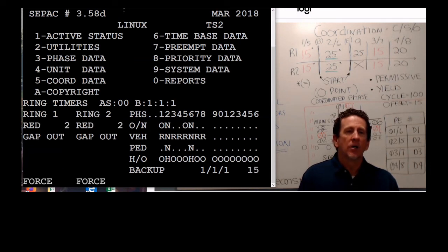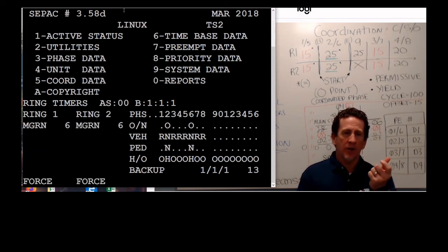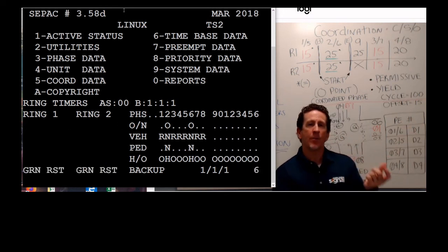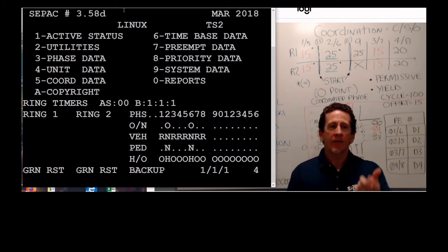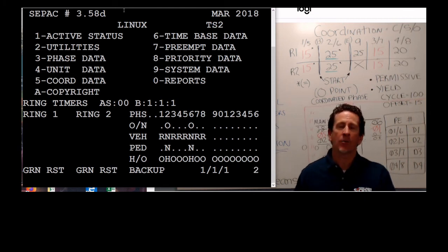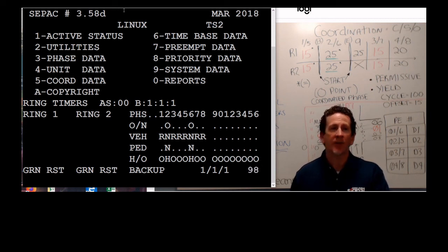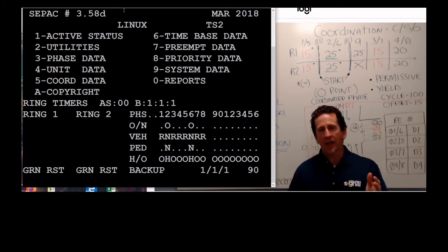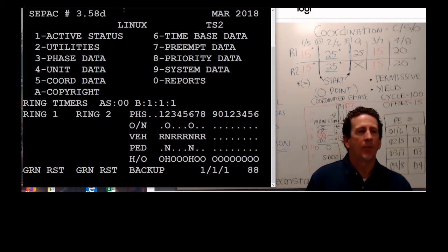But you could run into a situation where peer-to-peer is a programmed function. So if something crazy happens outside of the scheme of what we programmed the peer-to-peer to do, then you could impact how the preemption is working. If you were going to go to peer-to-peer schemes, you'd have to think of every possible scenario that could happen, so it's covered under peer-to-peer. If you leave it as preemption, then it just works organically how the system goes.